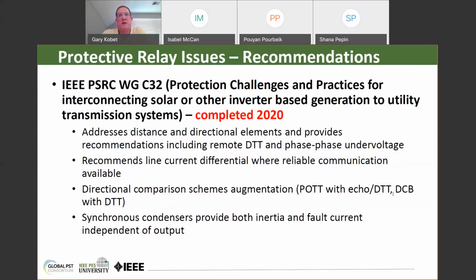Directional comparison schemes, such as permissive overreaching and directional comparison blocking. The permissive schemes may need echo, weak feed echo, and possibly direct transfer trip. Another thing that their report mentions is that synchronous condensers provide a couple of different benefits. Of course, they bring their own maintenance challenges, being rotating machines, but synchronous condensers still provide inertia and also fault current independent of output. So that's something else that the industry may want to consider.